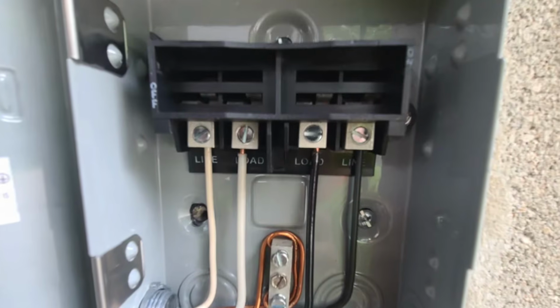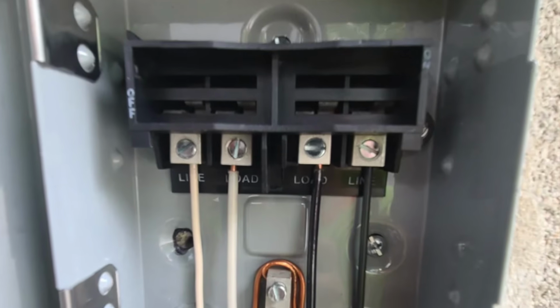I literally just did a job last year where I went behind another guy and I started simply pulling on things, pulling on wires to make sure everything was good and tight, and things were just falling apart, falling out of the bus bar where the wires were landed and so on, falling out of spade connectors that had been crimped on there, piss poor. And I said to the guy, hey, this is not good. This can create heat. This can be problems for this system and grounding issues like we were just talking about.